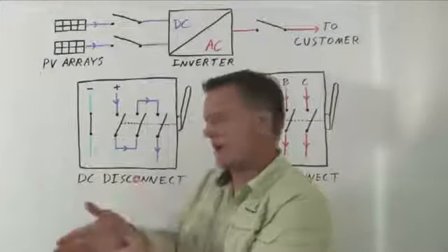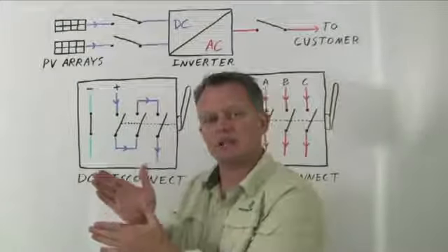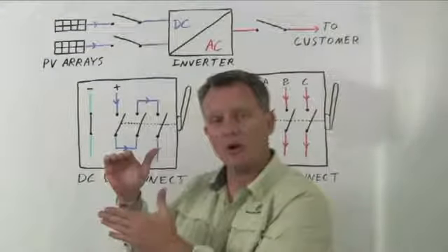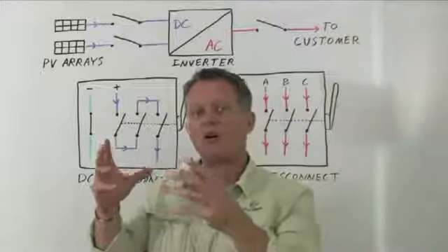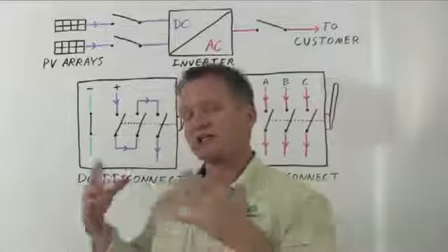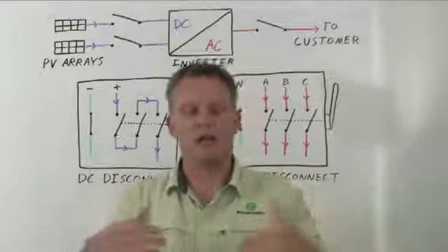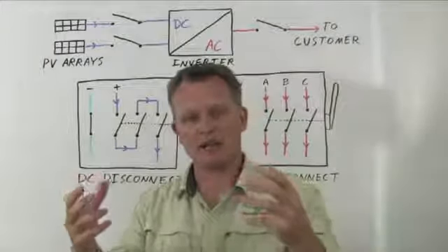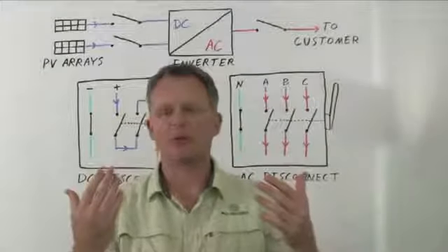Well, here's what happens. When you open up that switch, you think the current stops immediately, and that's not the case. What actually happens is that current continues to flow even through the air gap in the form of an arc. Now, that arc puts out an enormous amount of heat, and that heat, if it's not extinguished quickly, can damage components, can damage material, can actually hurt personnel. So these load break disconnect switches have to be designed in such a way where that arc extinguishes quickly.